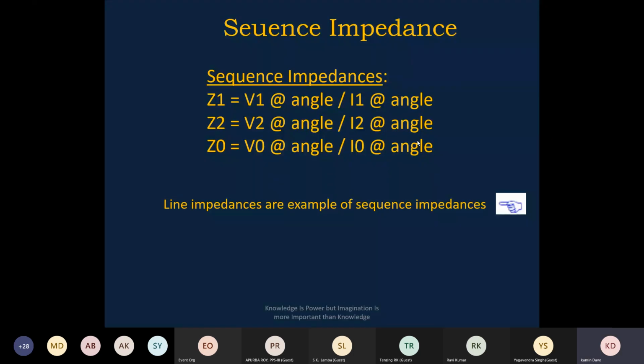And we also calculate the residual compensation factor to cover the tower footing resistance and arc resistance in a fault in a transmission line. For that, we use Z0 minus Z1 divided by 3Z1. That is the residual compensation factor. These factors can be calculated in other ways also, but in any way, the zero sequence and positive sequence impedances are involved.